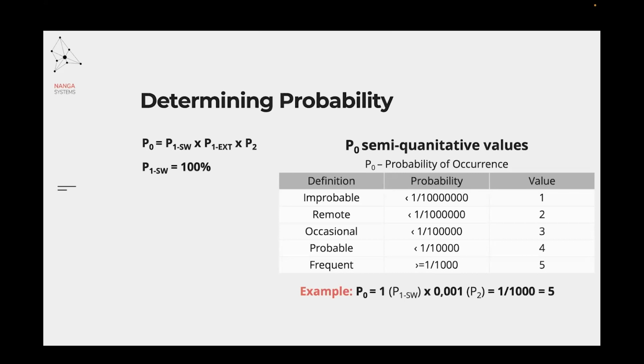And if we would not separate P0 into P1 and P2, then the typical approach would be, which is actually not correct, to say that P0 is 100%. But that would mean that the failure will happen, and the harm that is represented by P2 will also happen, but we wouldn't want to release such a device that will 100% result in a hazardous situation that will lead to a harm. So this is the reason why we have to separate these two.